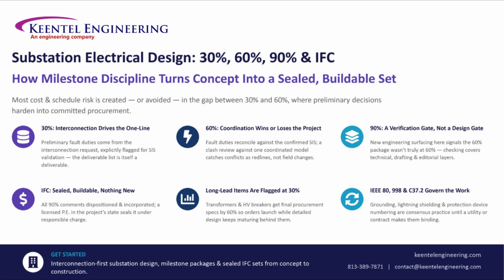By 60%, coordination is what actually wins or loses the project. Fault duties get reconciled against the confirmed study, and a proper clash review against one coordinated model catches conflicts as red lines on paper, not expensive changes in the field. 90% is a verification gate, not a design gate. If brand new engineering is surfacing at this stage, that's a signal the 60% package wasn't really at 60%. And by IFC, every 90% comment is dispositioned and incorporated, and a licensed professional engineer seals the set under responsible charge. Sealed, buildable, nothing new.